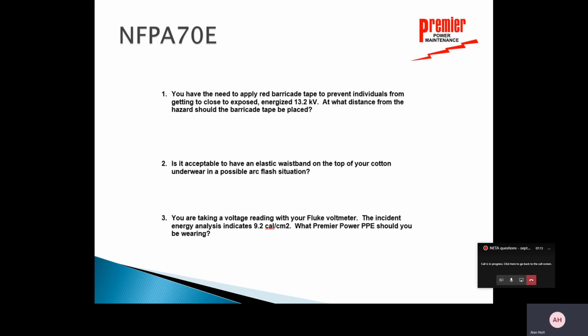Okay, and so you have to look in the charts in 130.7, section E, part 2. It talks about barricade tape. It has to be placed no closer than the arc flash boundary. Okay, so we have two choices here. It's either the arc flash boundary, which should be on the label, or the limited approach boundary. So we can't get it any closer than that. So basically, whichever is the furthest away from that actual energized 13 kV, that's where the red barricade tape should be.